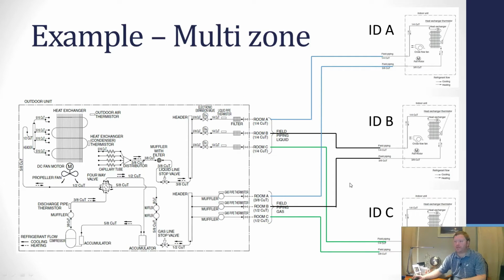So now let's go ahead and take a look at an actual schematic. Again, just like we talked about before, it's doing the same thing from a refrigeration circuit perspective, except this time we just have multiple ports. So out of your compressor, you're still going to have that hot gas that goes through that four-way valve. Then it's going to go down through basically a header or a manifold, and hot gas is going to come out of all three of your ports. And then what I did here is I just labeled our pretend line sets different colors so you could see where the line sets need to go to indoor unit A, indoor unit B, and indoor unit C.